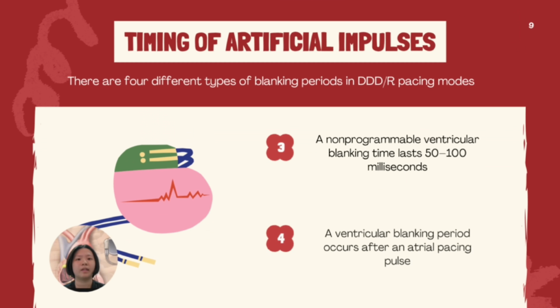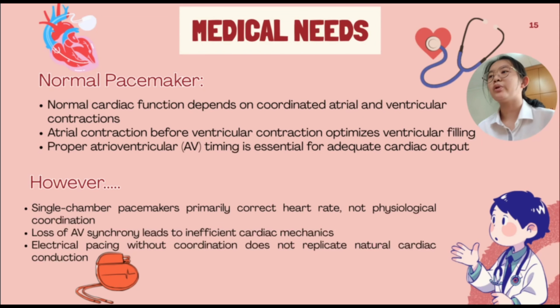In dual-chamber pacing, each ventricular pace or sense event is followed by a non-programmable ventricular blanking time to prevent improper detection of the intrinsic R wave or ventricular pacing pulse. This period lasts 50 to 100 milliseconds and is dynamically adjusted based on signal strength. Additionally, a ventricular blanking period occurs after an atrial pacing pulse to prevent sensing of the far-field atrial stimulus. Next, let's look at why normal heart coordination is so important and what happens when it is lost.